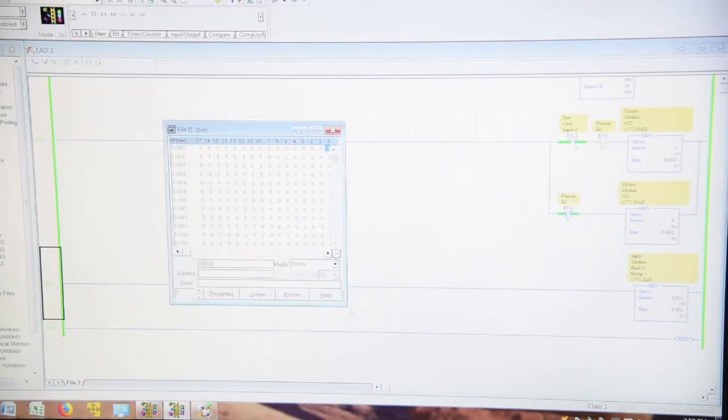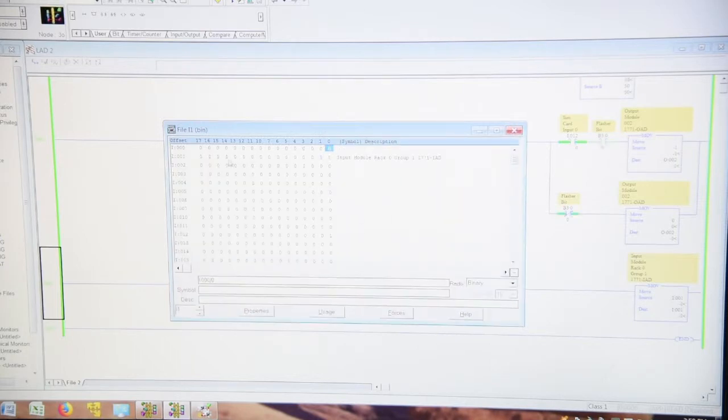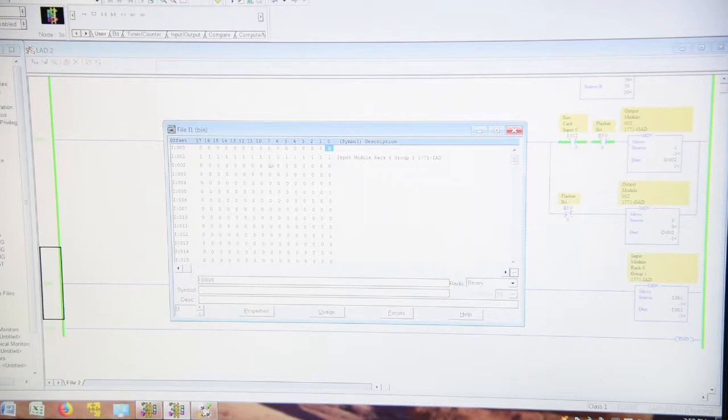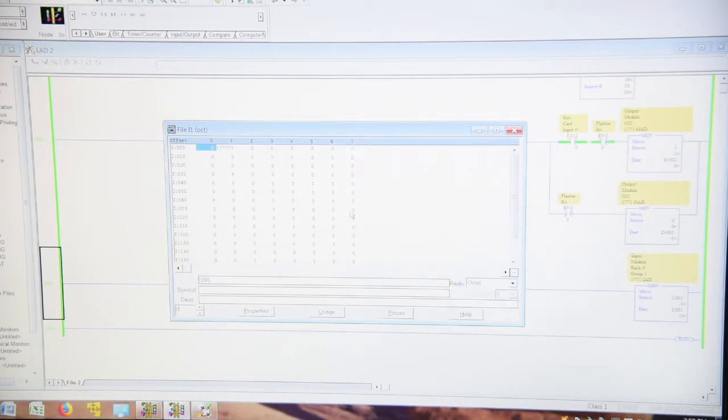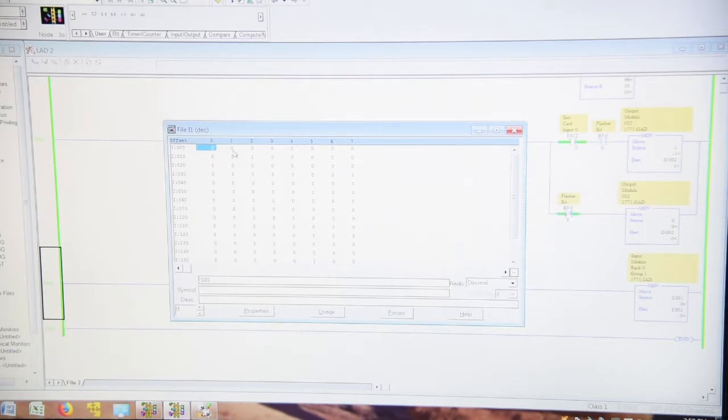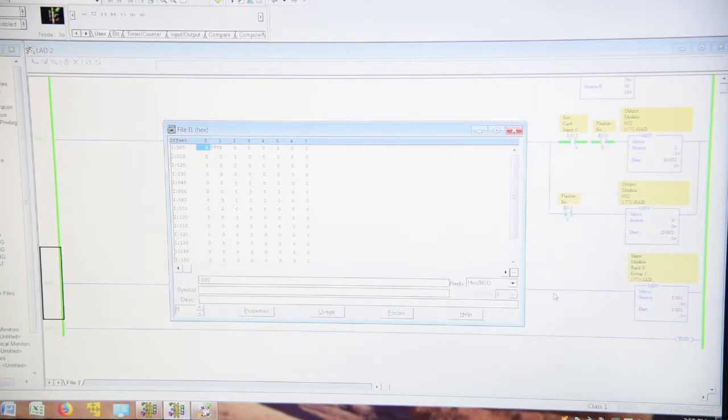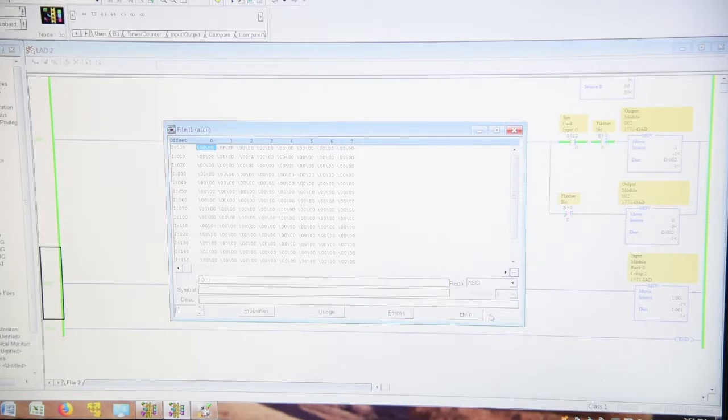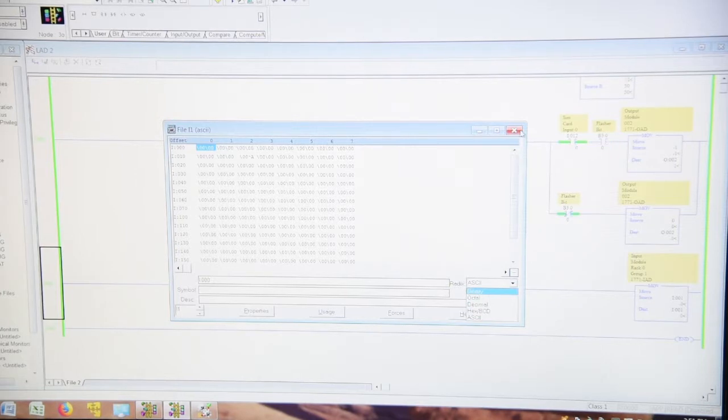If we go into our data table here, which is our input data table, you can see here all 16 bits are going on and off in binary. In octal we have one and four sevens. In decimal we have zero and minus one. In hex BCD we have FF, FF, and zero. And in ASCII, if you ever want to do it, is slash FF, slash FF, or zeros. So ASCII and BCD are basically, but all of these have their uses.